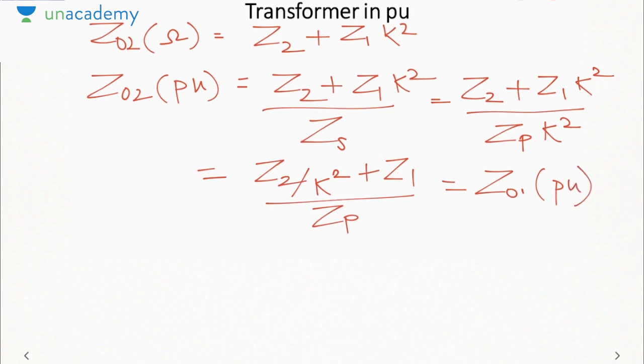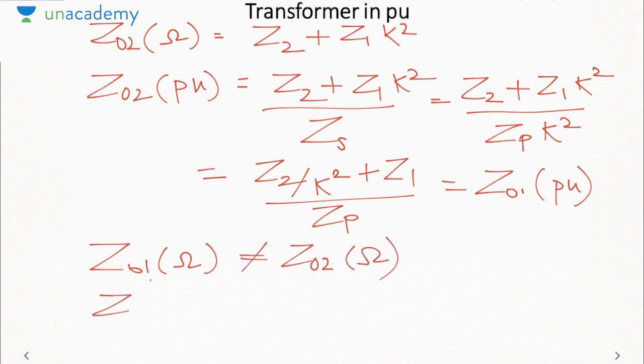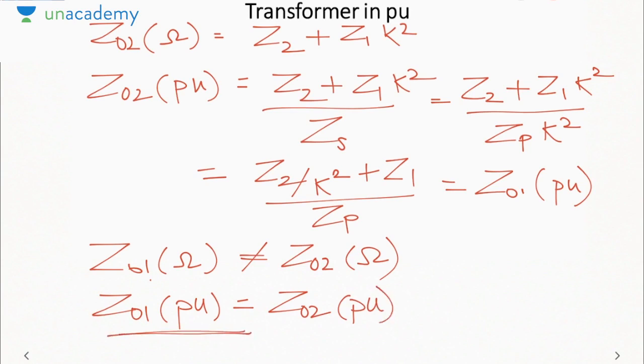So from here we can see that though Z01 in ohms is not equal to Z02 in ohms, Z01 in per unit is equal to Z02 in per unit. So the per unit impedance referred to primary and secondary is the same. But remember, this is Z01 and Z02 specifically; Z1 in per unit will still not equal Z2 in per unit.